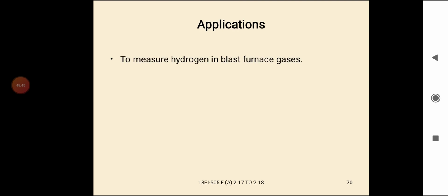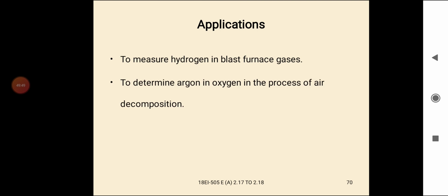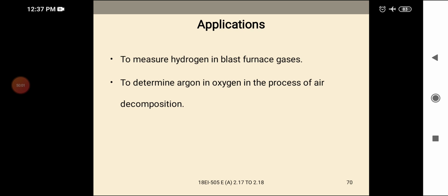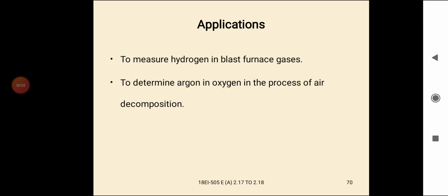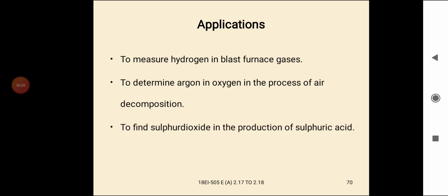Applications: to measure hydrogen in blast furnace gases, to determine argon in oxygen in the process of air decomposition, and to find sulfur dioxide in the production of sulfuric acid.